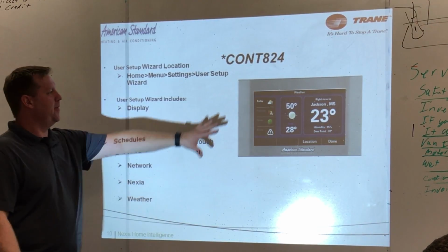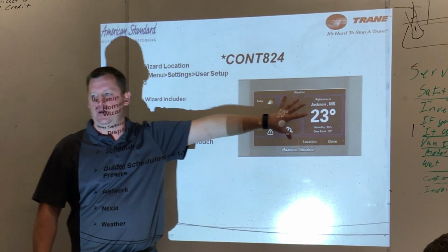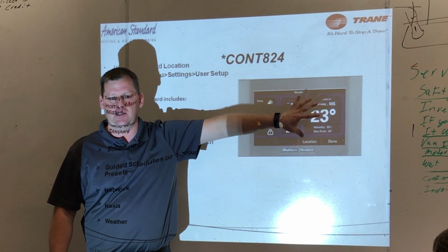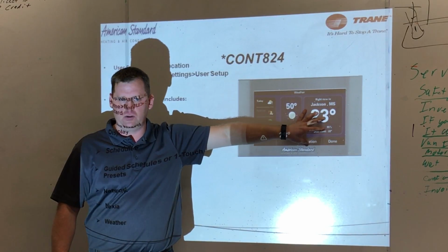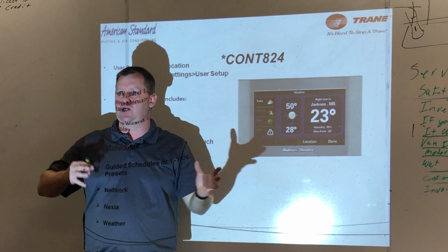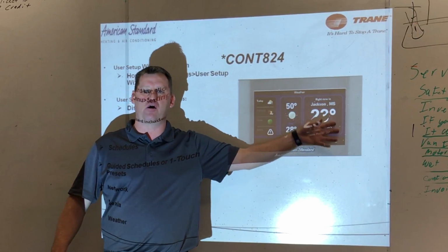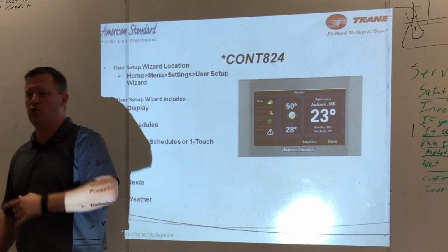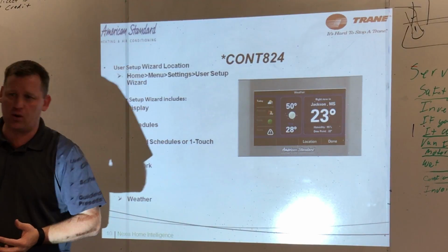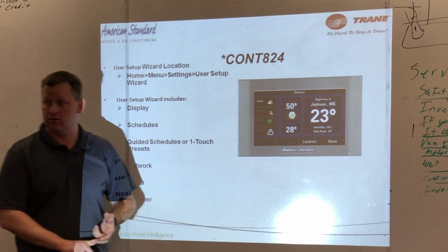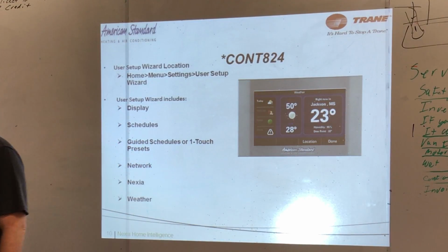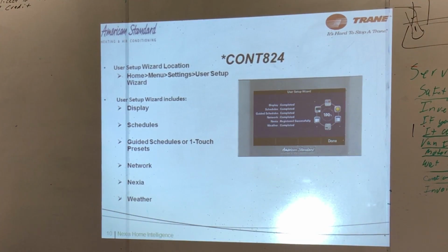Now remember, with internet weather, this does not give us the ability to control outdoor temperature or control a system based on outdoor temperature. We need a hardwired outdoor stat to do auxiliary lockouts, compressor lockouts, those type of things. We cannot do lockouts based on internet weather.